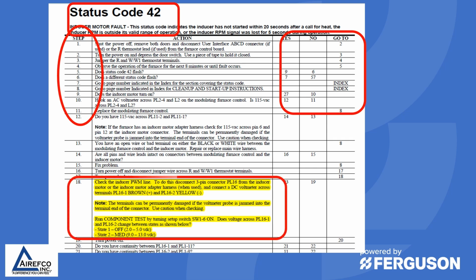In step 18, you will notice that you are checking the inducer pulse width modulating line. And so between the brown and the yellow wire, when the motor is off, you should have 2 to 5 volts DC. And when it's calling for the motor to run, you should have 9 to 13 volts DC. So you see, it's very important to have these voltages so you know whether the board is putting the correct voltage out to the motor through the harness, or if the motor is not receiving it and it's a defective motor itself.